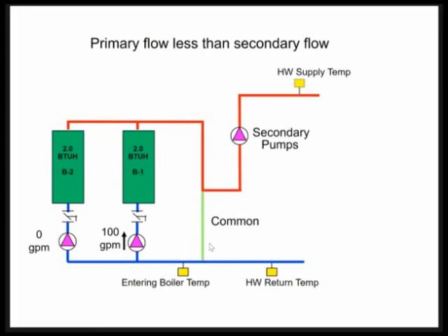Well, what happens if primary flow is less than secondary? I mean, if primary flow is greater than secondary means sometimes our return water temperatures are elevated, maybe we want to run primary flow less than secondary. Well, when that happens, it usually means there's been a load introduced into the secondary than more than the boiler running or two boilers running can handle. What does that look like?